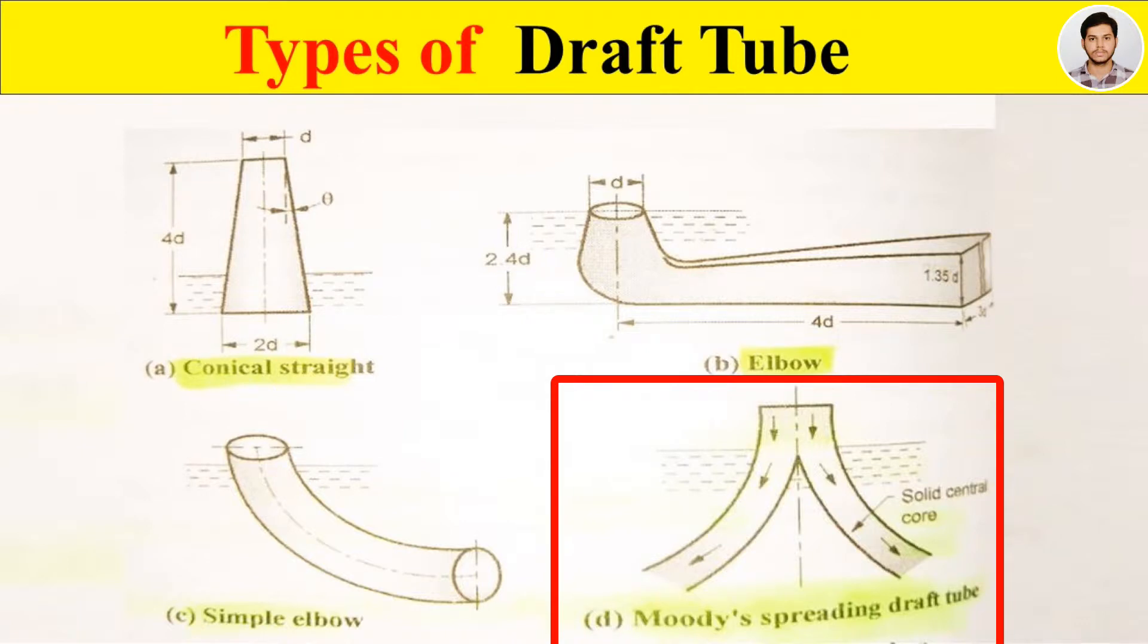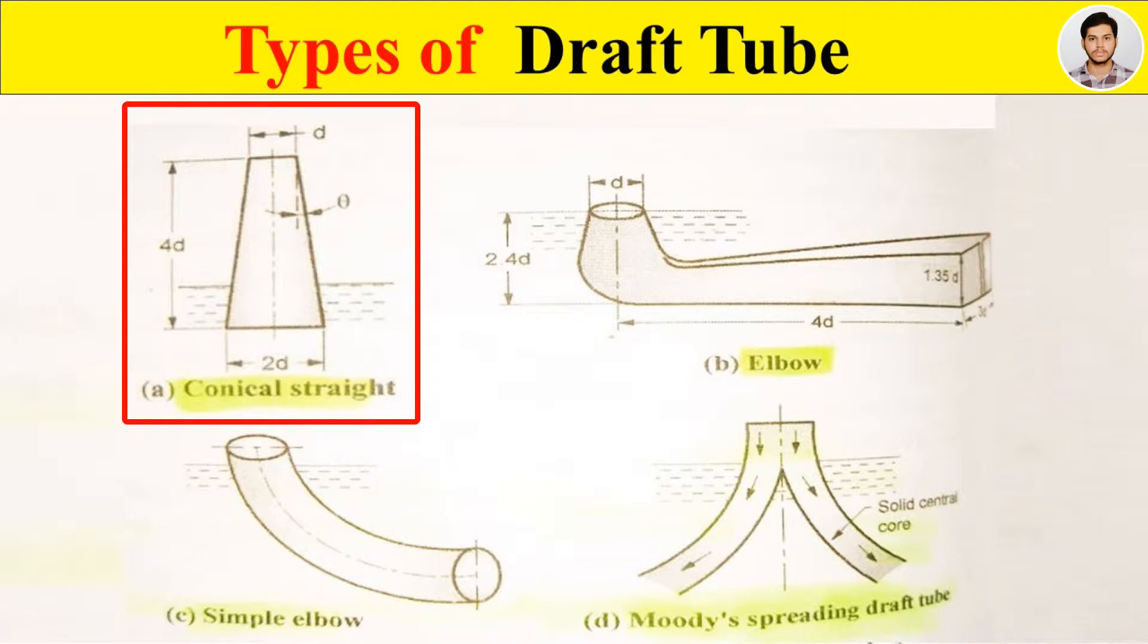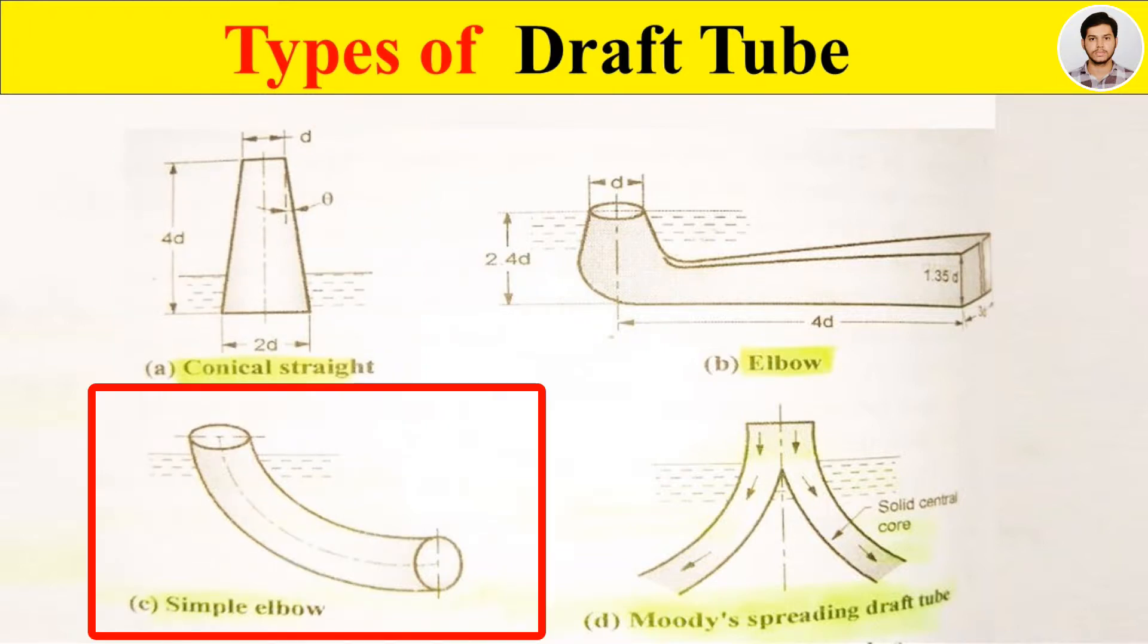First we see conical draft tube, an earlier design of draft tube with conical straight divergent shape. The taper angle of the divergent portion of the tube is of great importance. If the taper angle of 20 degrees is large, it will cause the separation of flow from the walls of draft tube. In case the taper angle is small, the length of draft tube needed will be long, causing higher friction loss. It is fabricated out of mild steel plate. It has efficiency of 85 to 90 percent.